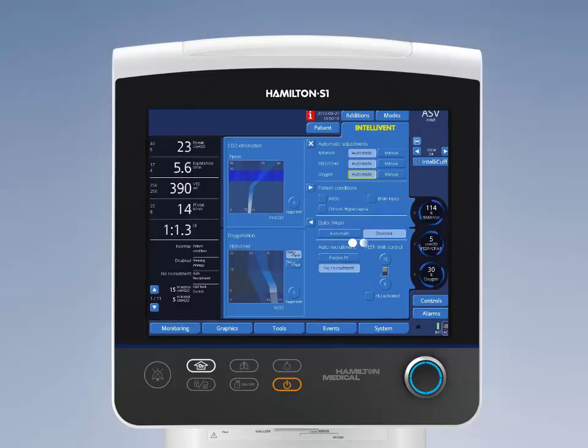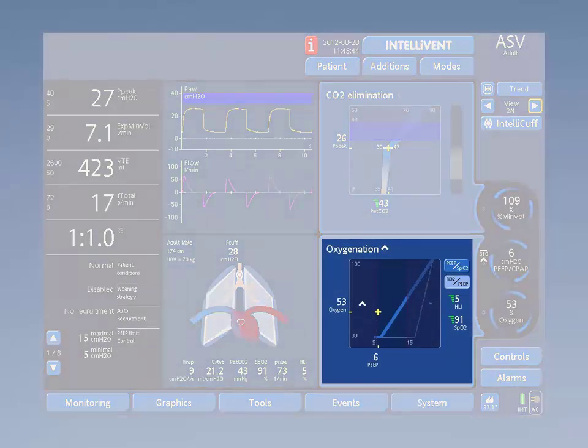Oxygenation is based on PEEP and FiO2 — PEEP to create open alveoli for oxygen uptake, and FiO2 because oxygen needs are increased during disease. At the start of IntelliVent ASV, the physician determines the range of desired SaO2. When saturation drops, FiO2 and/or PEEP will be increased, depending on the current settings of PEEP and FiO2 compared to the ARDS network PEEP/FiO2 table. The light blue zone is the zone where the PEEP and FiO2 controller are active according to the ARDS network tables.